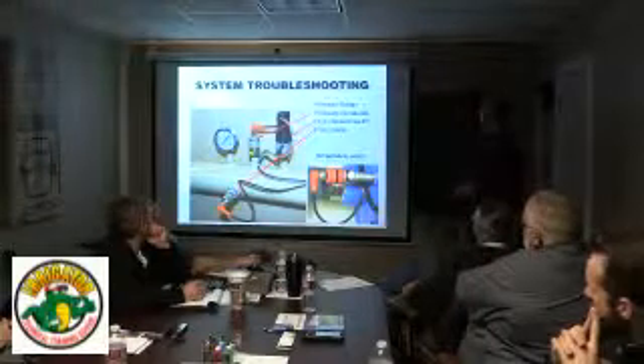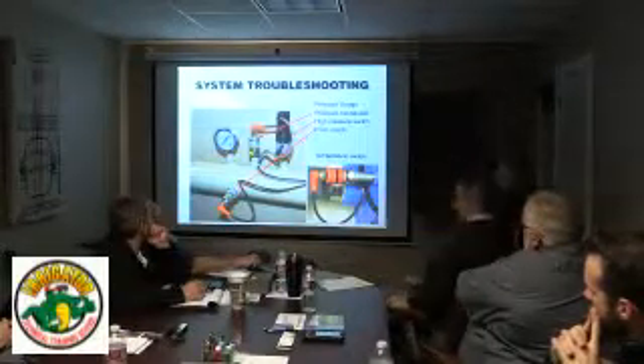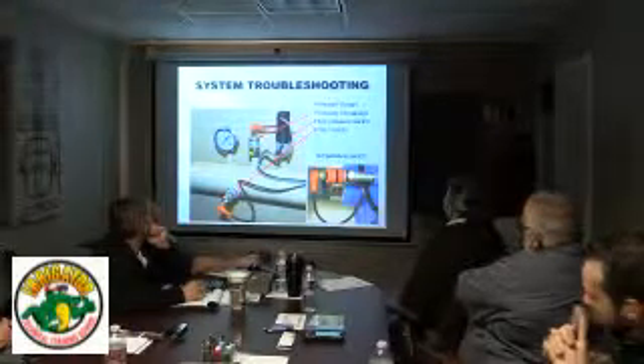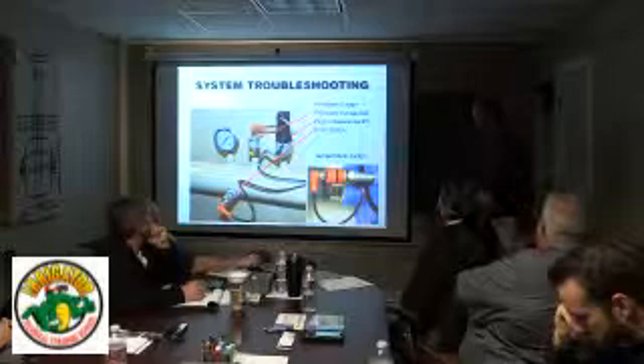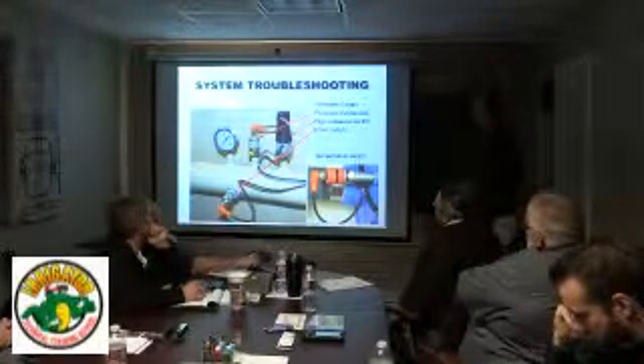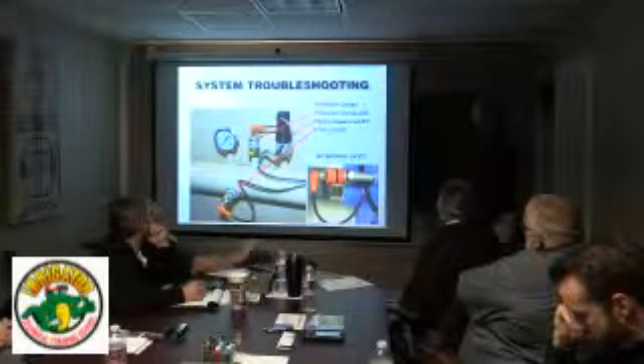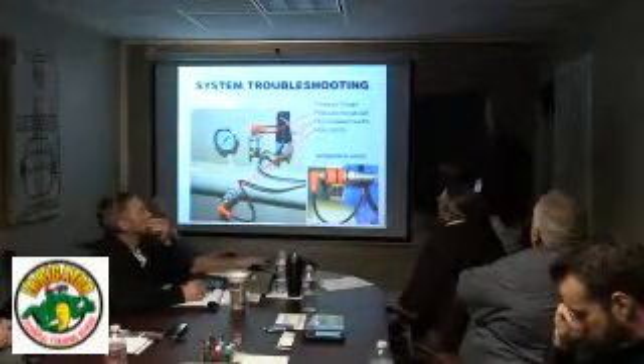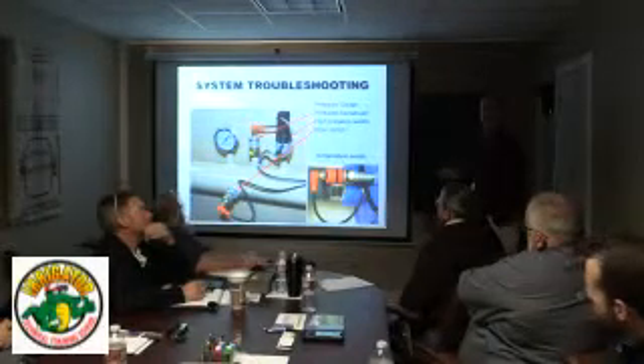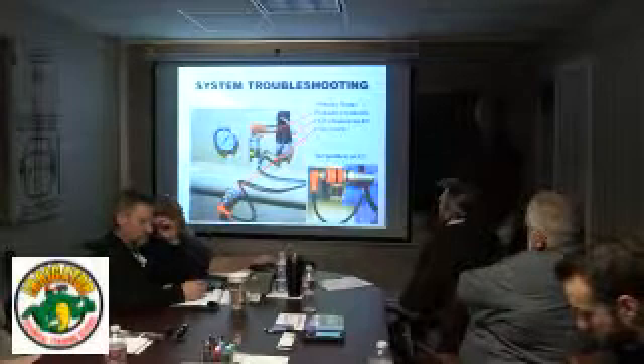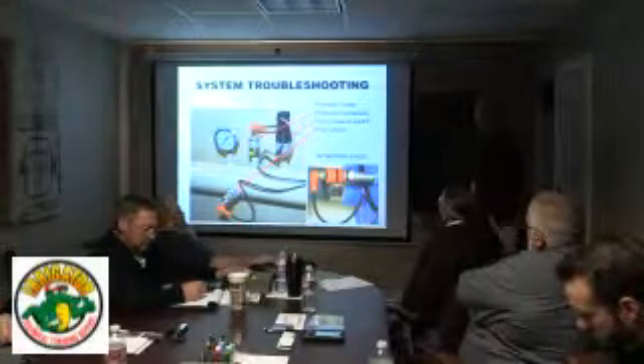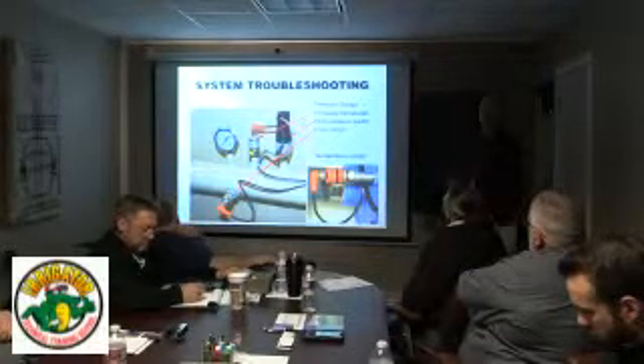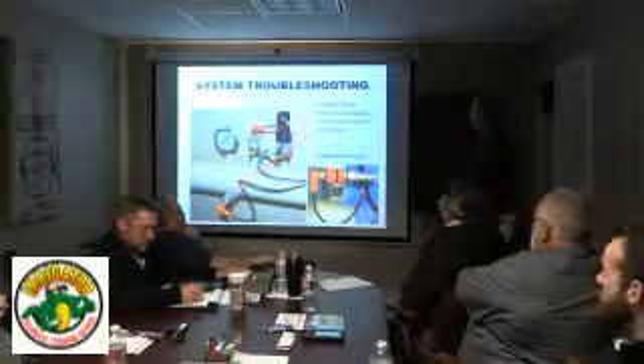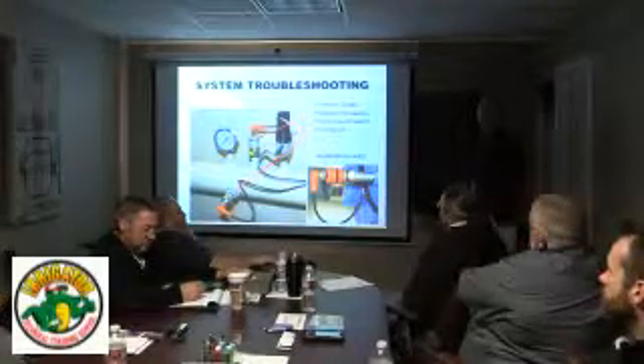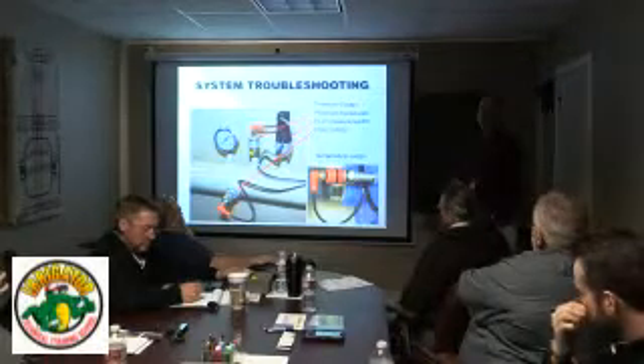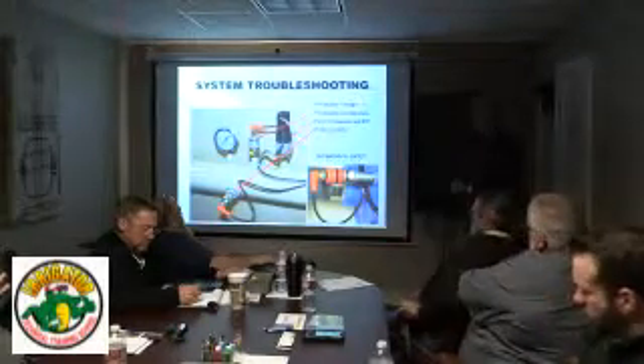So this is pretty typical of what you would see on one of our manifolds. Pressure gauge, pressure switch, high pressure switch, and transducer, and the temperature switch. We also have a flow switch. Now, like I showed before, that Seametrics flow meter, if it has a flow meter, it's not going to have a flow switch. If it doesn't have a flow meter, it probably is going to have a flow switch. We might use that for a couple reasons, either to sleep by flow or mostly for low flow protection. Occasionally a drive might not go into a sleep mode. You don't want to just sit there running and cook the pump with no flow.